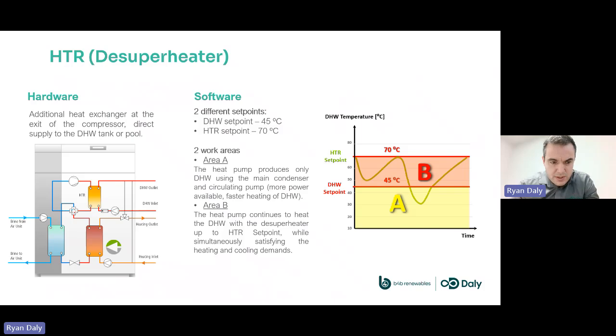So what the HTR will do is a second smaller plate heat exchanger inside the ground source heat pump. And once that gas in our system hits 56 degrees coming off the compressor, it opens up the secondary circuit and dumps that excess heat that's being generated into the hot water system or the swimming pool. So you can see in the graph on the right where you have your baseline temperature of 45, for example, and then the heat pump when it's on heating mode can be topping up the hot water to a higher temperature free of charge.